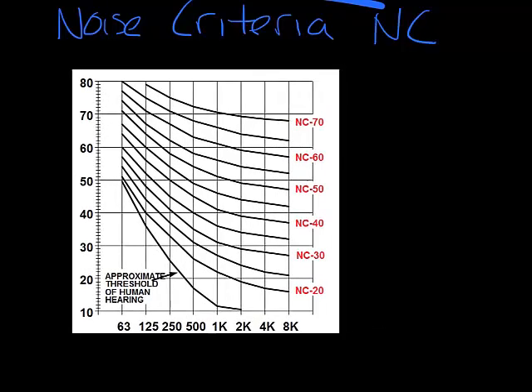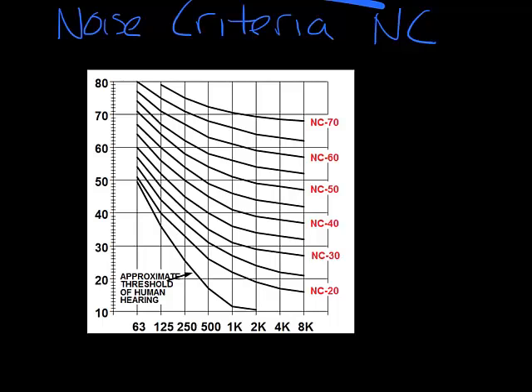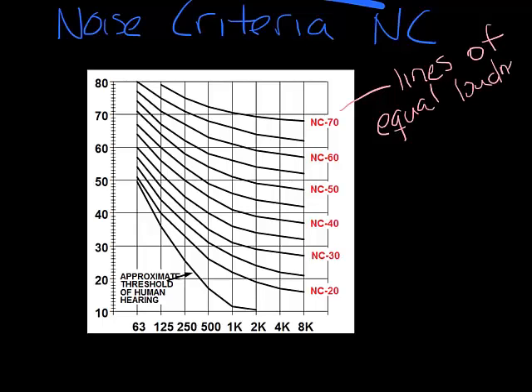The NC lines are essentially lines of equal perceived loudness. Every point on the NC line sounds as loud as the other points on the line. You can see that the NC curves have high decibels in the low frequencies. If you recall from the Sound Basics podcast, low frequency sounds have to be louder for us to hear them.